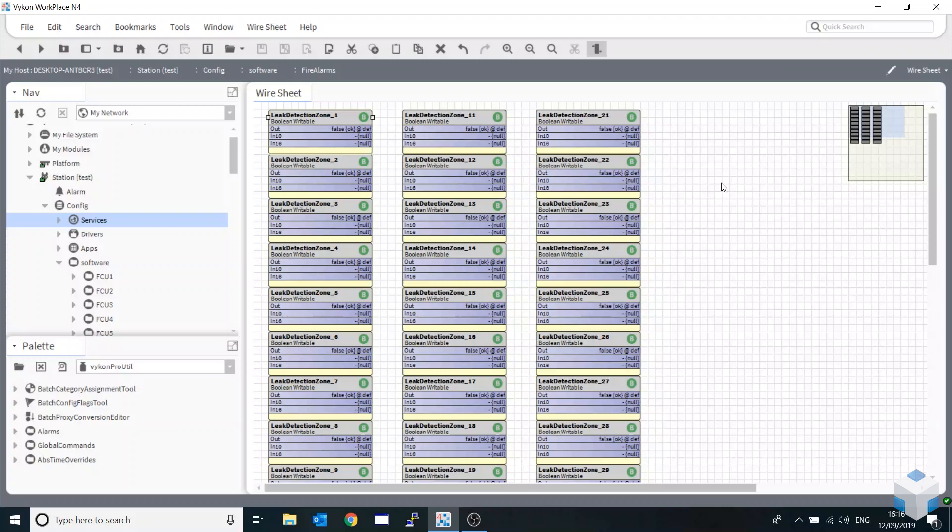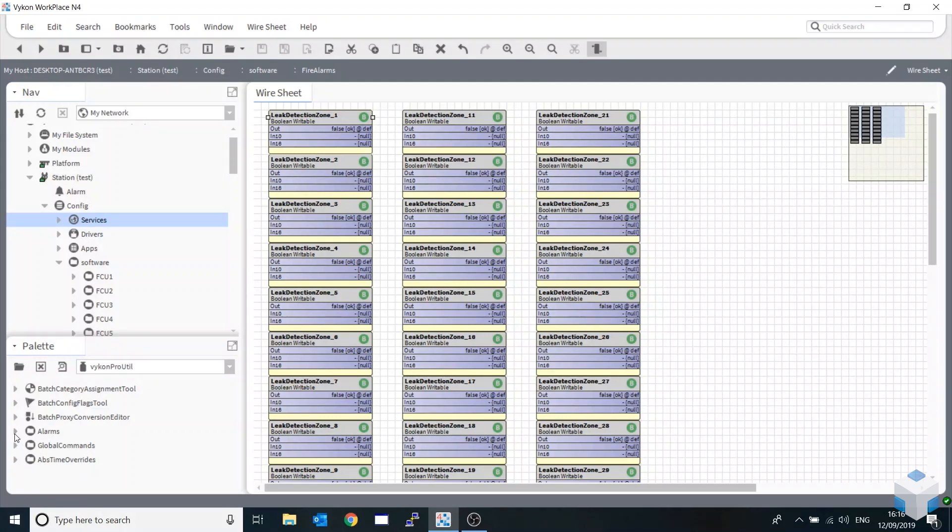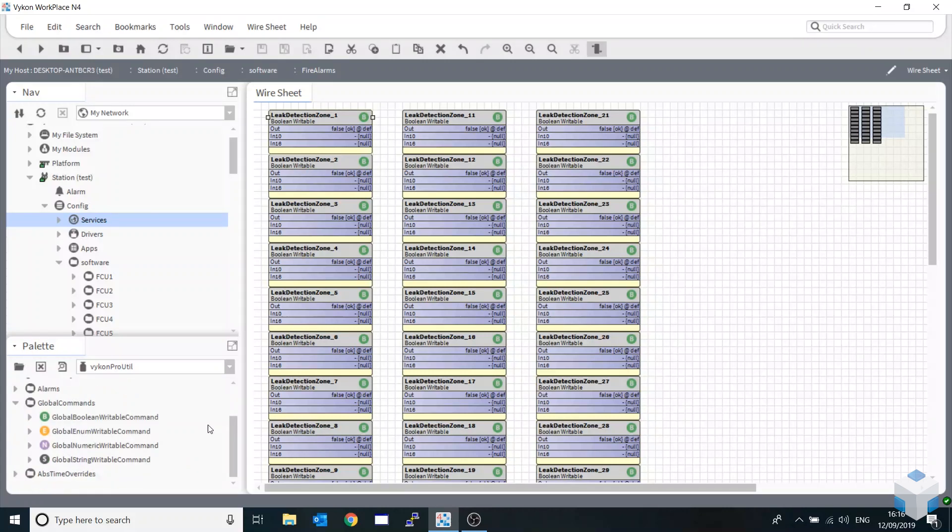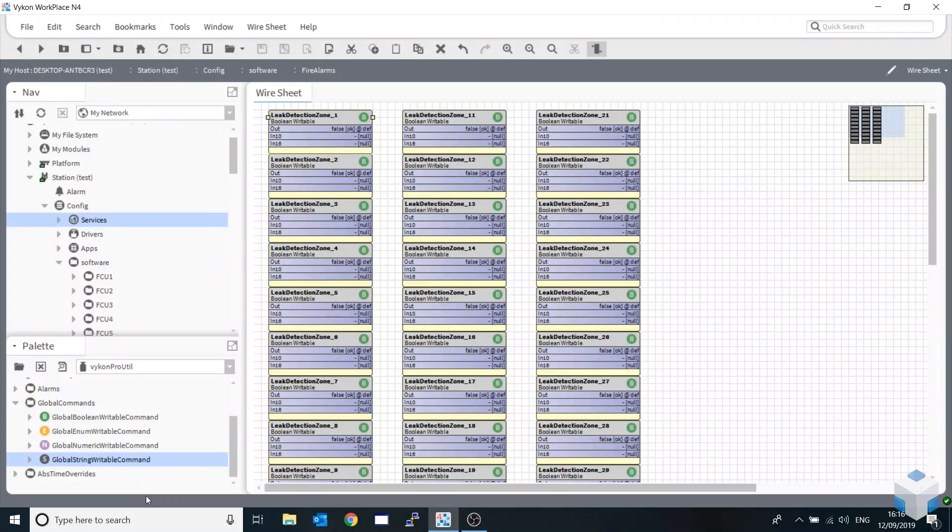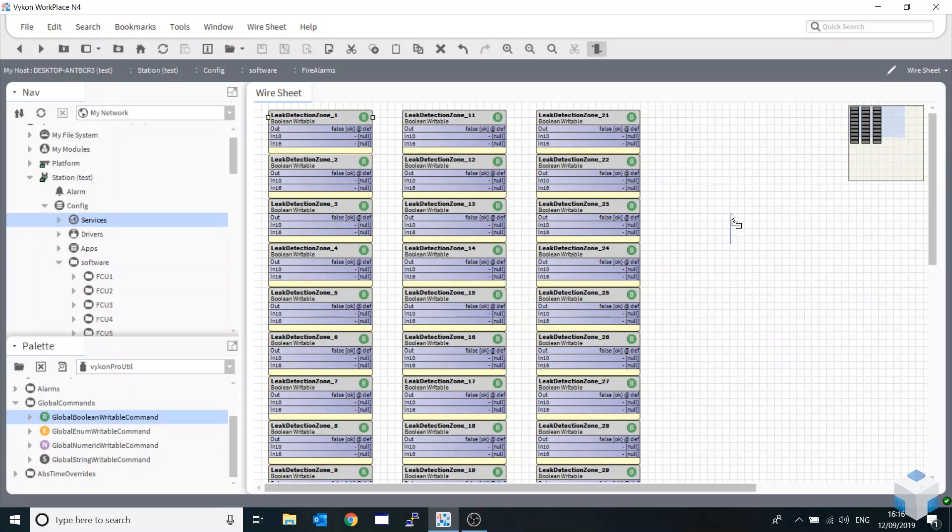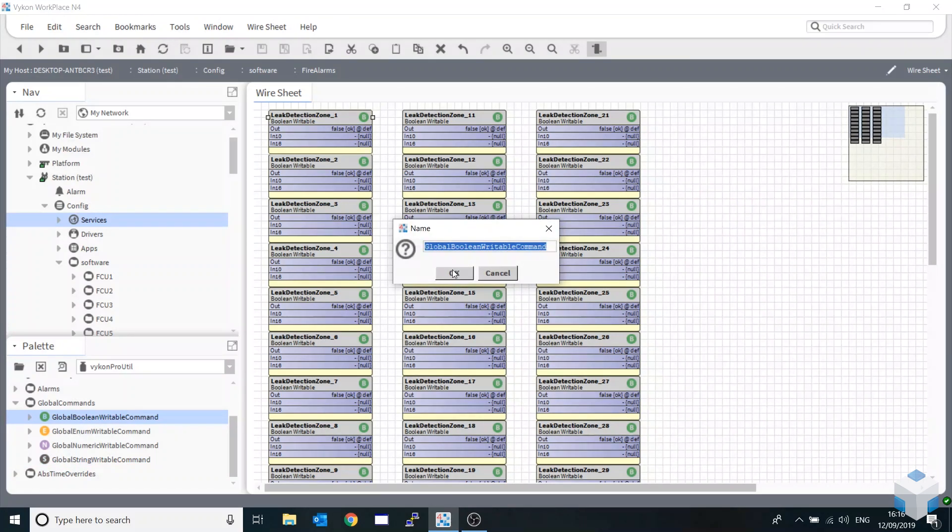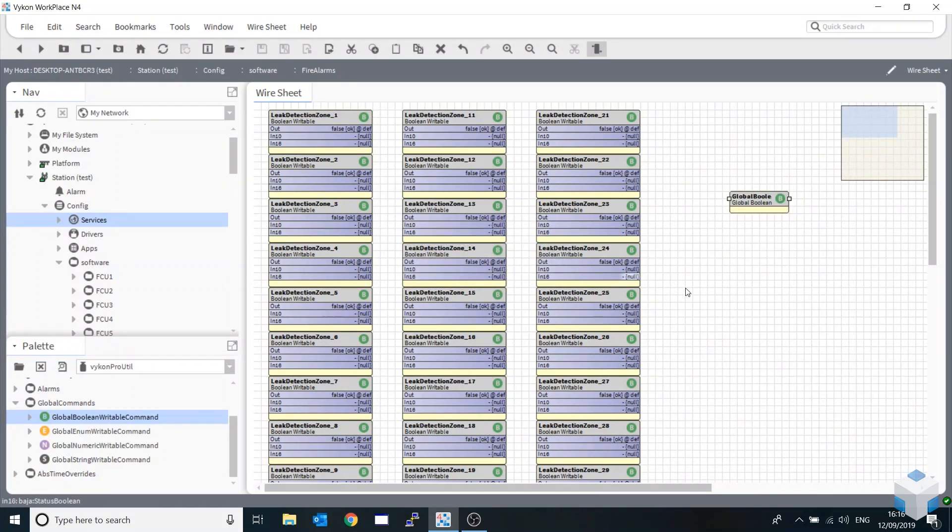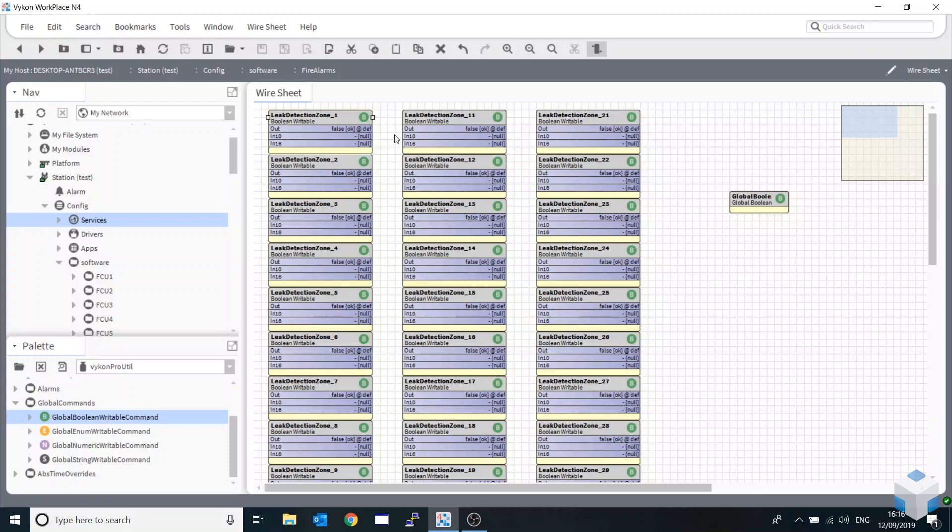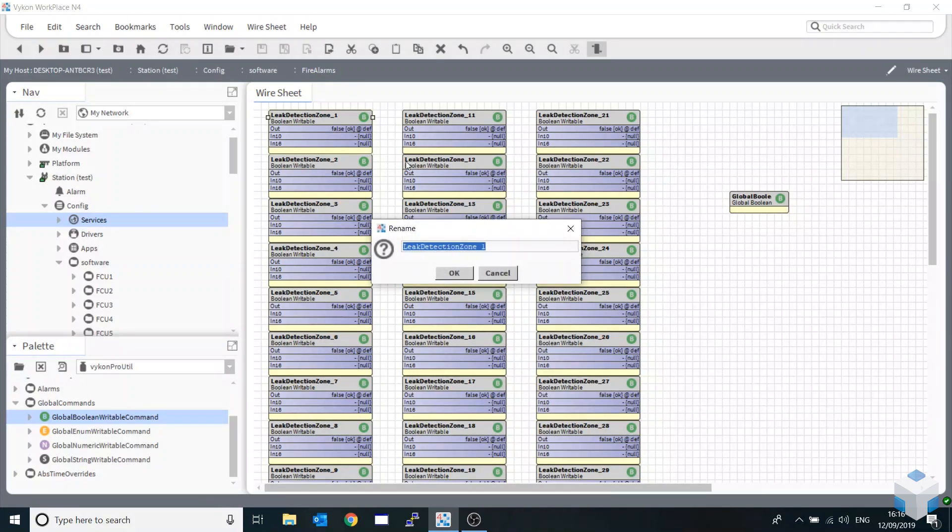You can override these 100% if they're numeric values. If you want to test boolean points and alarming to make sure everything's working correctly, these blocks are very useful. If we go into our vykonProUtil palette and expand global commands, we've got four different types: booleans, enums, numerics, and strings. I'm going to grab the boolean writable command and paste that in. I'll be using the naming convention of these points with wildcards. I'm just going to hit ctrl+R and copy my first part of my name.